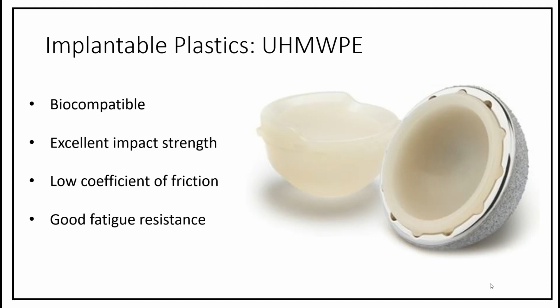UHMWPE, ultra-high molecular weight polyethylene, has been one of the common polymers used in the development of implantable orthopedic applications. UHMWPE is biocompatible, has excellent impact strength, a low coefficient of friction, and good fatigue resistance. For these reasons, it has been used for many decades to manufacture orthopedic applications used in the hip, knee, and other joints. Though the material has proven successful in these areas, it is not used in the development of load-bearing applications, such as spinal cages, due to its relatively poor mechanical strength compared to other polymer alternatives. While UHMWPE is considered to have a low relative wear rate, there have been concerns about tissue reaction to the wear particles and resulting implant loosening.